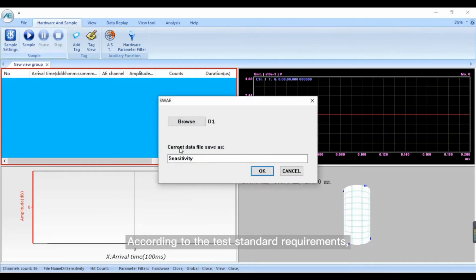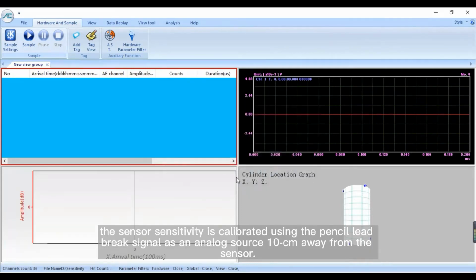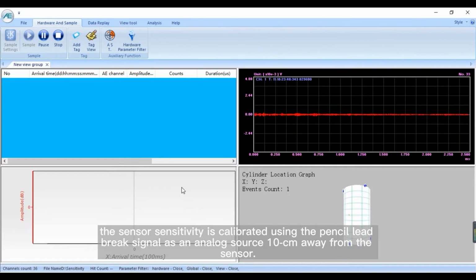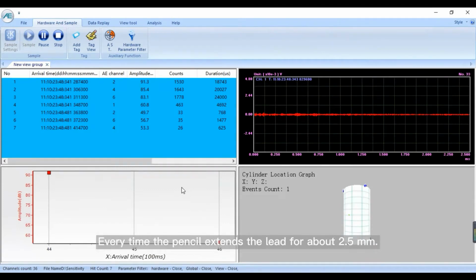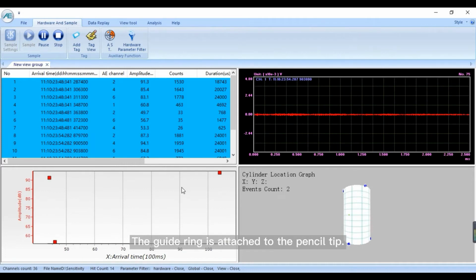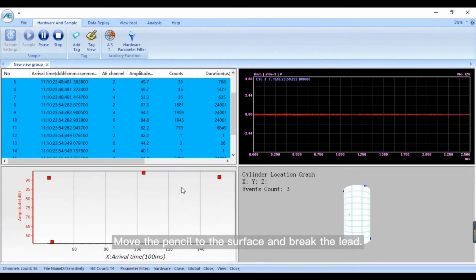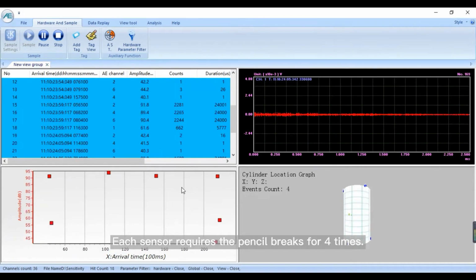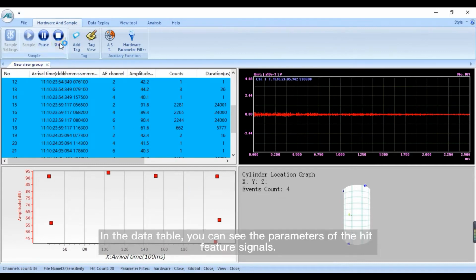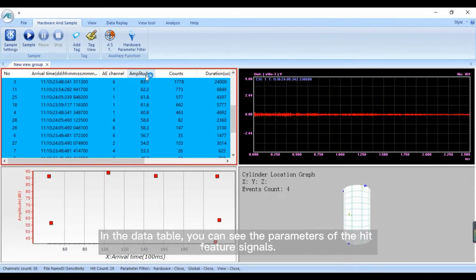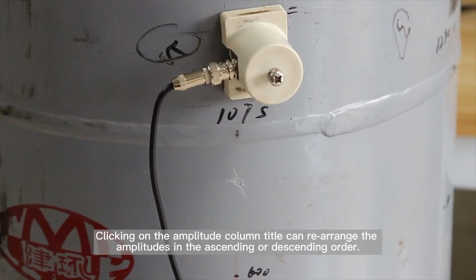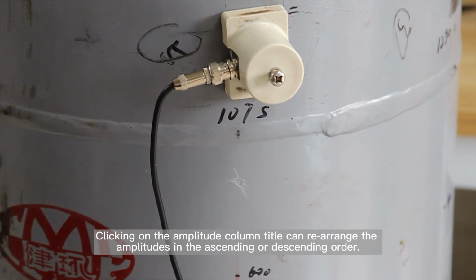According to the test standard requirements, the sensor sensitivity is calibrated using the pencil lead break signal as an analog source, 10 centimeters away from the sensor. Every time, the pencil extends the lead for about 2.5 mm. The guide ring is attached to the pencil tip. Move the pencil to the surface and break the lead. Each sensor requires the pencil breaks for 4 times. In the data table, you can see the parameters of the hit feature signals. Clicking on the amplitude column title can rearrange the amplitudes in ascending or descending order.